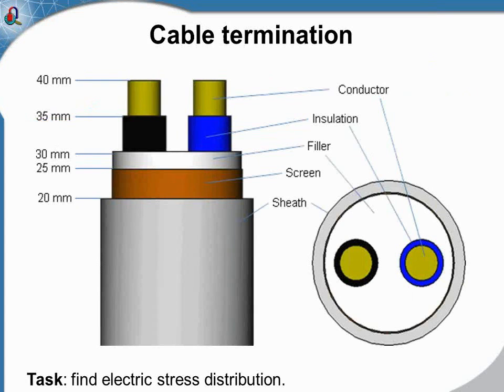The cable consists of positive and negative conductors covered with insulation. There is the filling and there is the sheath, and just behind the sheath there is a thin layer of the electromagnetic screen. The cable termination is the most loaded part of the cable system, and special measures should be taken to limit the field strength and assure safe and reliable operation.